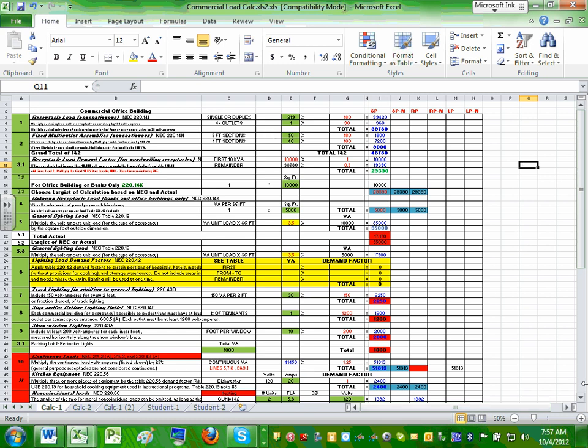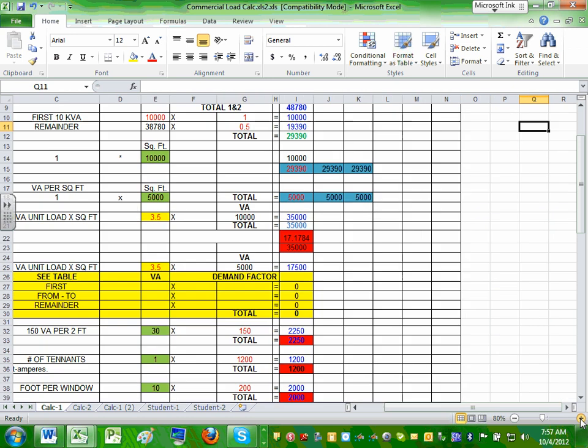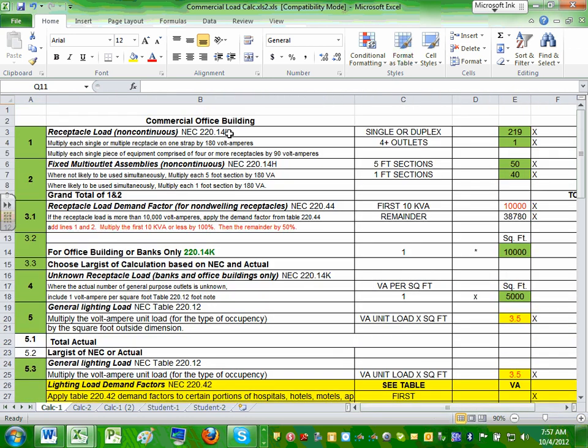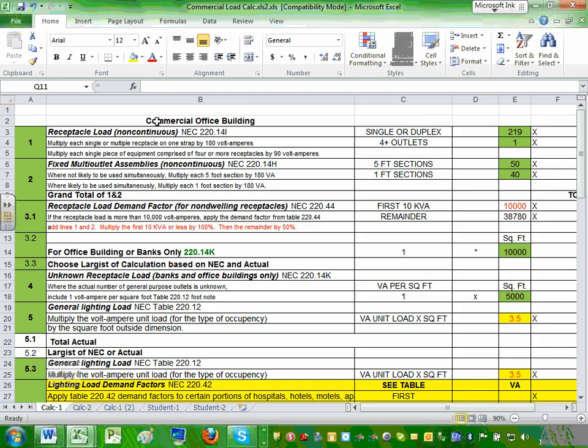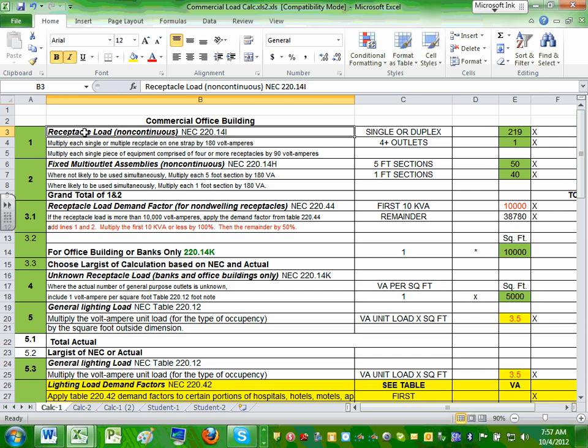Now let's go and do it step by step. The first type of load — and there are many ways of doing this, this is only one way — the first type of load you have to accommodate in a commercial building is the receptacle load. Your receptacle load is going to come from Article 220.14(i).